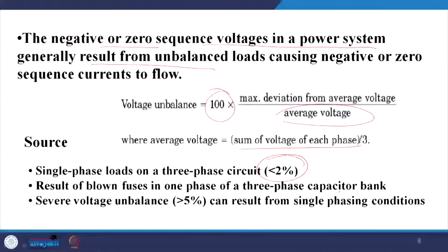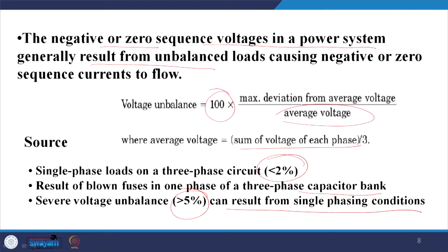A blown fuse in one phase of a three-phase capacitor bank may cause severe unbalance. Severe unbalance — more than 5 percent — can result from a single phasing condition. We will show how even typical single phasing conditions can be mitigated by the shunt active power filter.